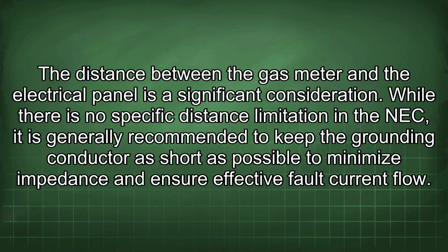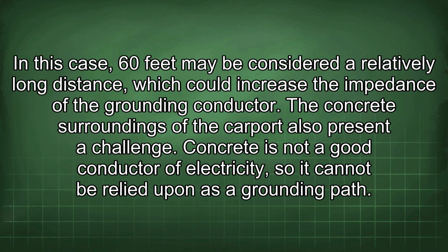The distance between the gas meter and the electrical panel is a significant consideration. While there is no specific distance limitation in the NEC, it is generally recommended to keep the grounding conductor as short as possible to minimize impedance and ensure effective fault current flow. In this case, 60 feet may be considered a relatively long distance, which could increase the impedance of the grounding conductor. The concrete surroundings of the carport also present a challenge.